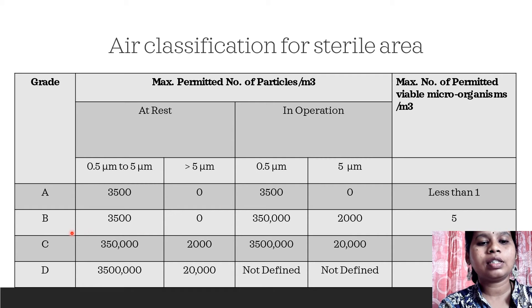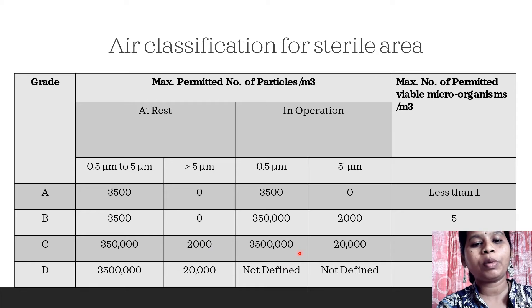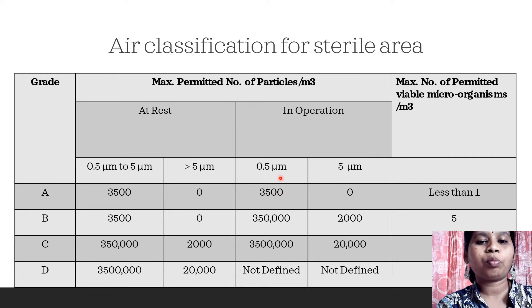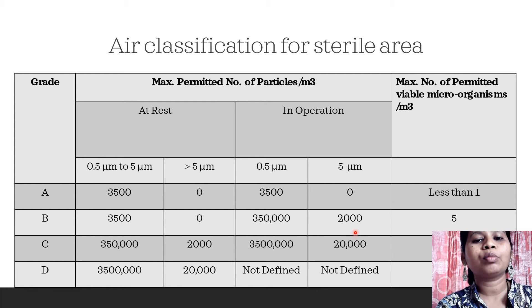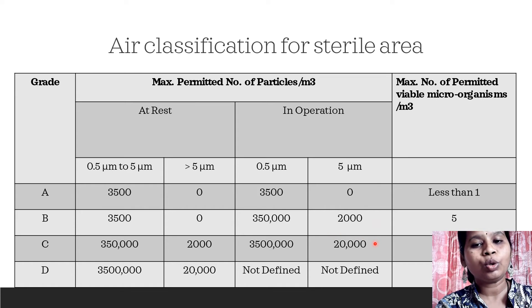For Grade B, which serves as the background for Grade A, it has similar conditions at rest, but in operation the maximum number of particles permitted differs. For 0.5 micrometer particles, 350,000 are permitted, and more than 5 micrometer particles are permitted up to 2000. The number of viable microorganisms permitted is 5.